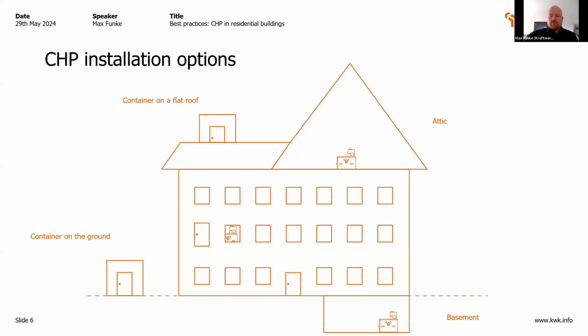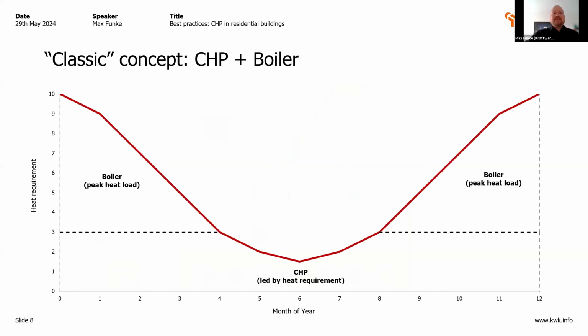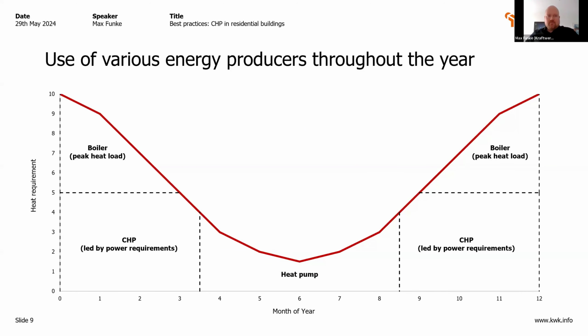And as Mr. Liesner and Mr. Voigt already told, it's quite easy to install a CHP unit next to a boiler. That was a classic concept in the last decades, I would say, with the CHP unit running for about 6,000, 7,000, 8,000 hours a year. But this has changed a little bit. Nowadays in Germany, we are using CHP units in addition to a heat pump, as was already explained. CHP units in the wintertime with a little bit higher electric output and heat output, and heat pumps in summertime in combination with photovoltaics, which makes a great combination, on the financial side as well as on the emission side.